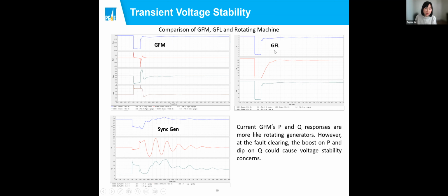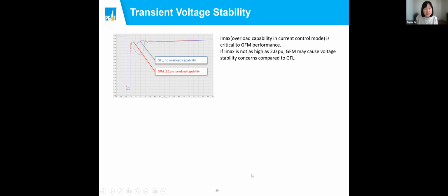And for the grid following inverter on the right hand on the top, I will have to put a caveat that a grid following inverter can perform like this, but it needs to be properly tuned in the controls. And based on my experience reviewing the models and working with manufacturers, sometimes it's not perfectly achievable. But let's say we have a perfectly tuned control in the grid following inverter. You can see upon fault clearing, in this case the Q response is in the green on the bottom. So you can see it quickly boosts up the Q, and then there will be a more gradual recovery of the P. And that's obviously better for transient voltage recovery compared to the performance from the grid forming and the synchronous machine. So these are the differences.